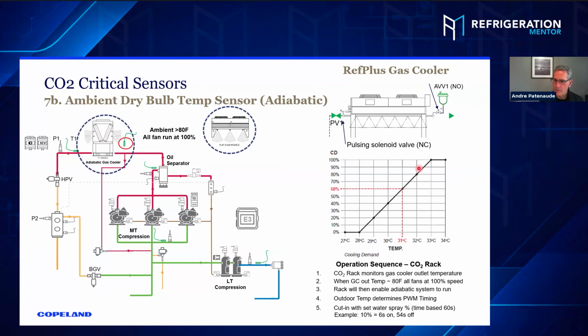You can see down here from their table that at around above 28 Celsius, the water flow starts, and it works off of a 60-second period, okay? At 31 degrees or 88 degrees Fahrenheit, it says that you would have a 60% water flow. So they use a pulse width modulated system: 60% of 60 seconds is 36 seconds on, 24 seconds off. So you have that misting, and the moist air hits the coil, and that's how you get the adiabatic feature. So that's how they run their gas coolers. So if you lose that temperature sensor, you lose the ability to get those fans to turn at 100%.